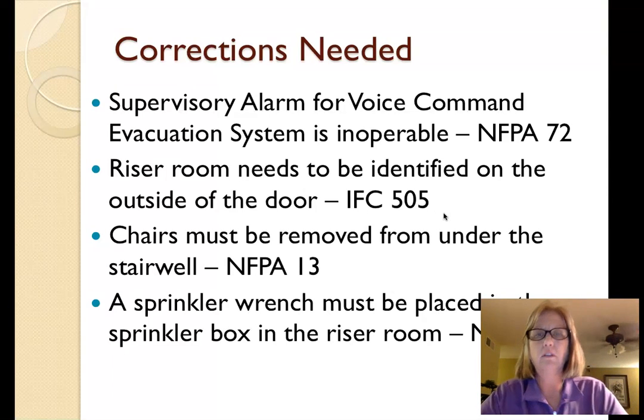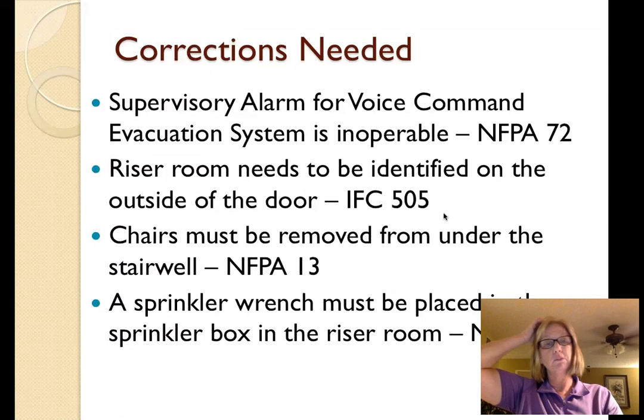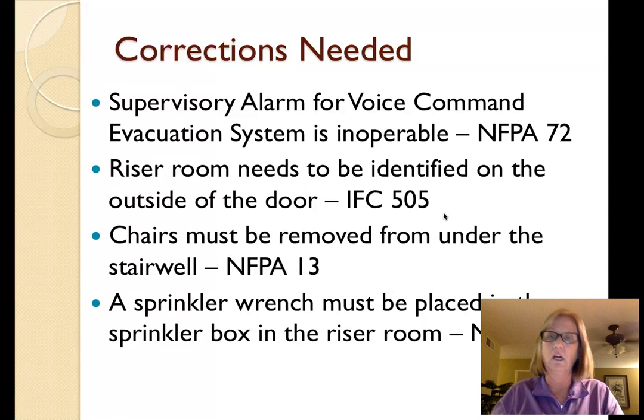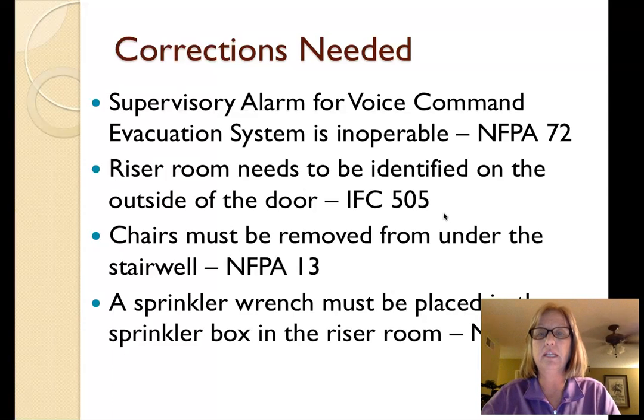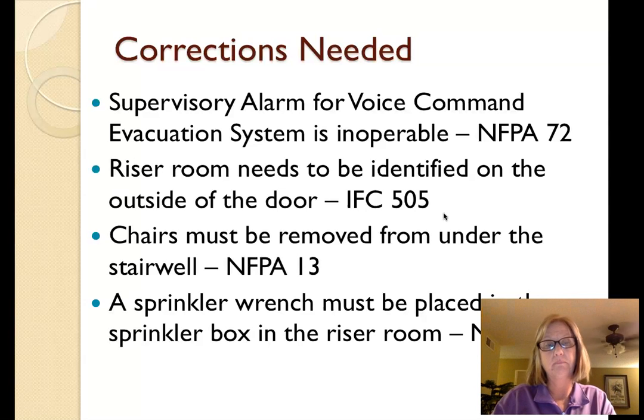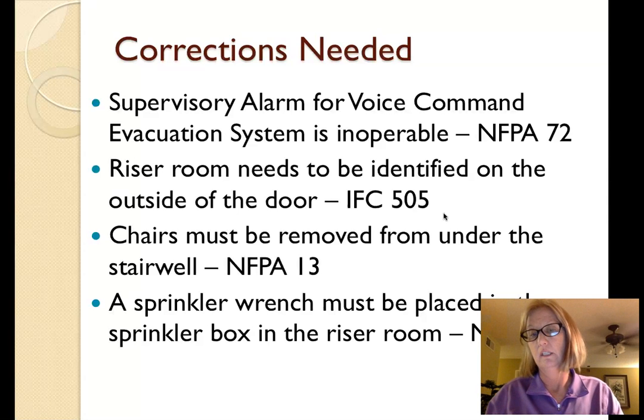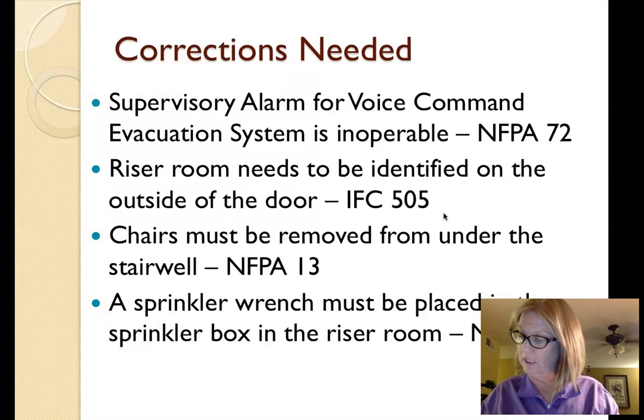The supervisory alarm for the voice command evac system was the major concern and is inoperable and has to be fixed. The riser room needs to be identified on the outside of the door per the International Fire Code 505. The chairs must be removed from under the stairwell per NFPA 13. And of course, a sprinkler wrench needs to be placed inside the sprinkler box in the riser room per NFPA 13.